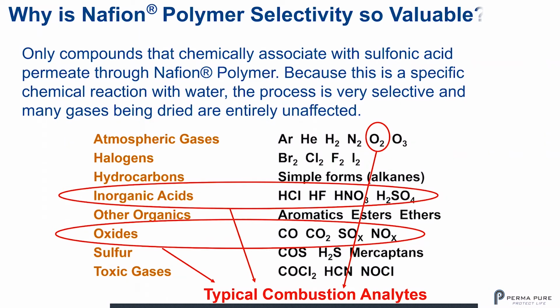And that is so important for industry, and that's why our whole company has been so successful over the years, because we've been able to exploit this very favorable property of the material that has become so valuable. So if you're doing any kind of analysis with atmospheric gases, halogens, hydrocarbons, inorganic acids, other organics shown there, oxides, any type of sulfur, or toxic gases, a PermaPure Nafion polymer dryer will remove the water while keeping those components intact.